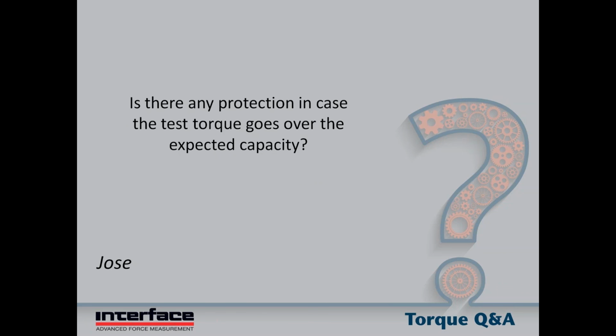Is there any protection in case the torque goes over expected capacity? Certain torque sensors have overload protection built in, and that would be a mechanical stop that protects them. Those are typically lower capacity reaction style sensors. We also have dual range sensors that allow, say, a high overload, but also measuring at a very low range using the second range. Those have their limitations though, and they're not necessarily as good as using a low capacity sensor to make the low capacity measurement, but they do allow survival of the higher torques.